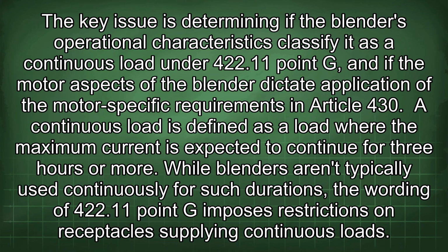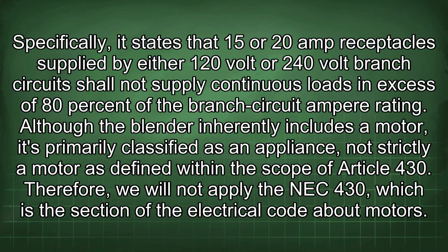A continuous load is defined as a load where the maximum current is expected to continue for 3 hours or more. While blenders aren't typically used continuously for such durations, the wording of 422.11.g imposes restrictions on receptacles supplying continuous loads. Specifically, it states that 15 or 20 amp receptacles supplied by either a 120 volt or 240 volt branch circuit shall not supply continuous loads in excess of 80% of the branch circuit ampere rating.